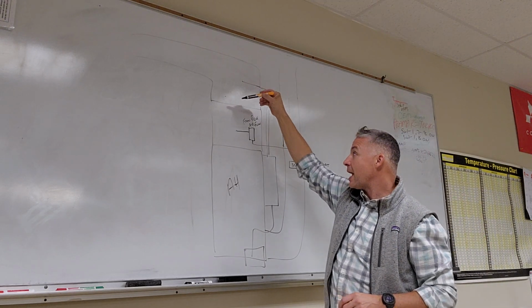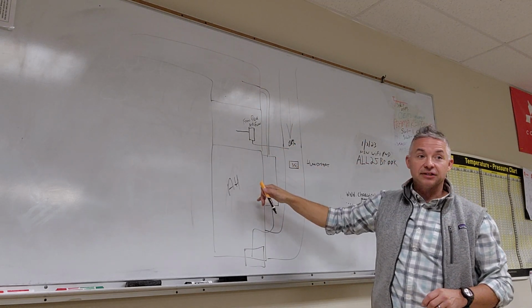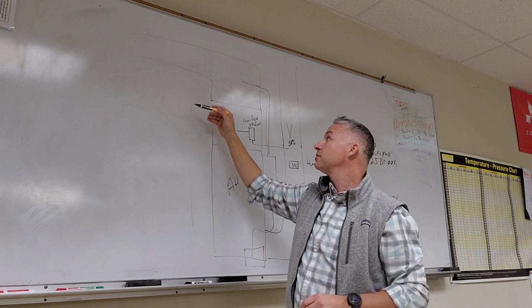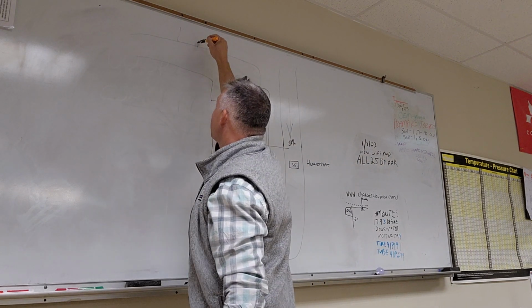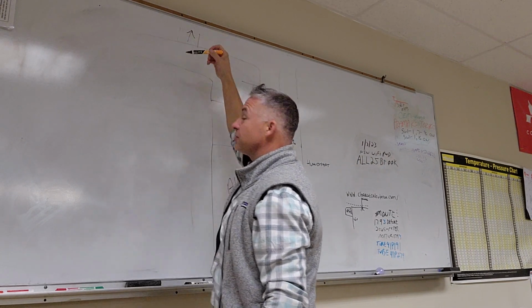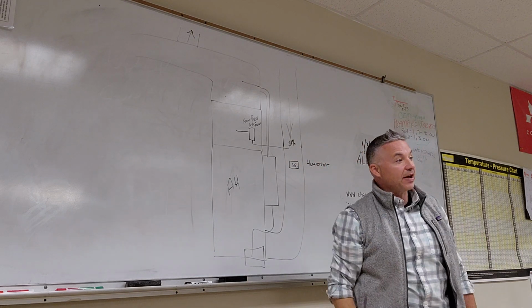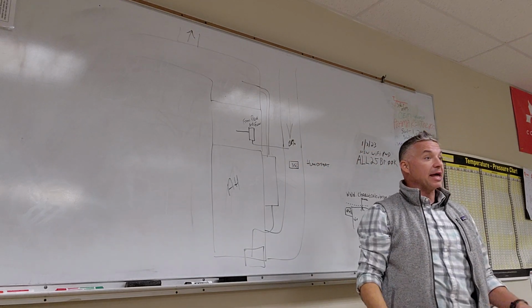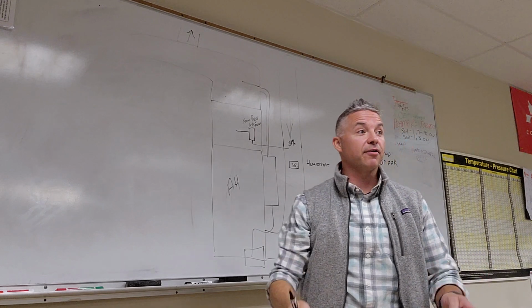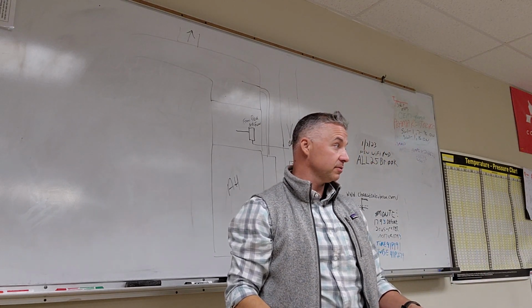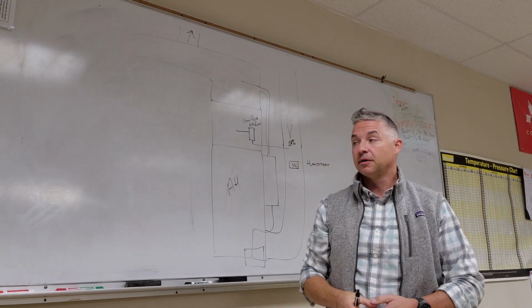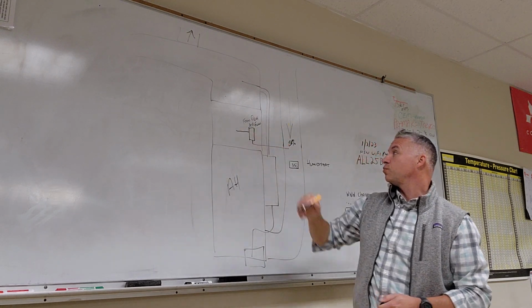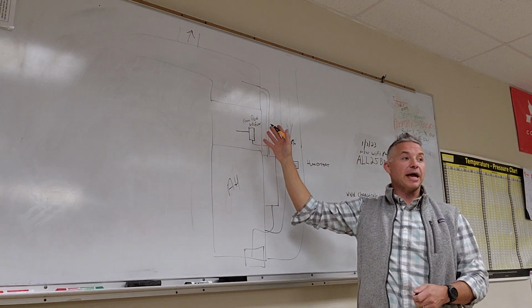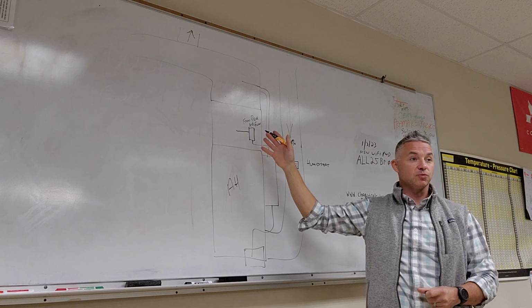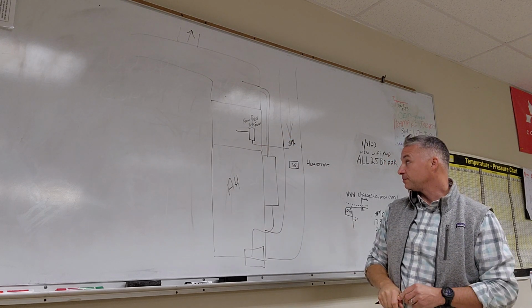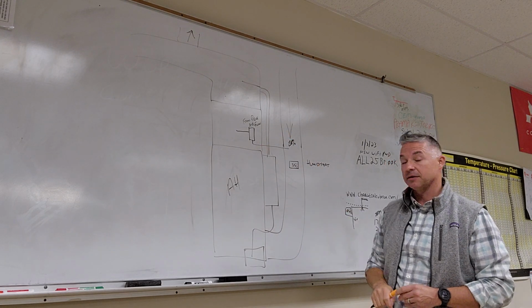You also are going to make it rain in there, which could leak water down inside your air handler and damage some components. And you're also going to have some vents that are going up into the house. You're going to get some raw steam pumping out of those vents, possibly. And in some of the houses we work in, we've got wood floors with very expensive wood grills that can be damaged. Okay? So we want to use what we think is the best way to actually prove that we have airflow, that the fan is working. So we have an airflow switch, and we have a humidistat. Okay?